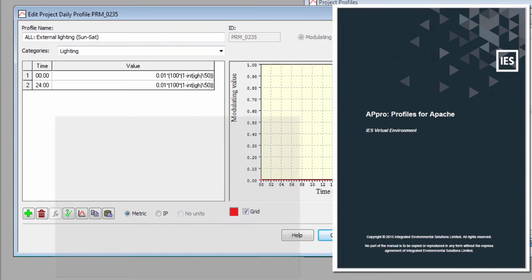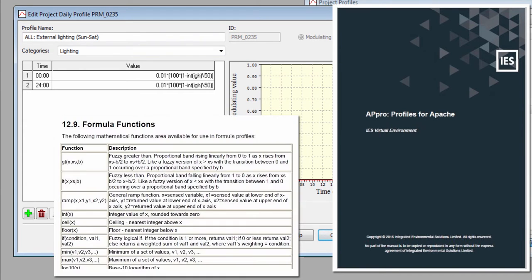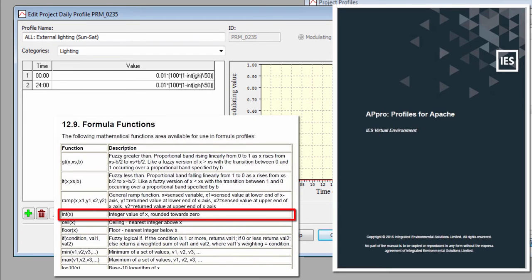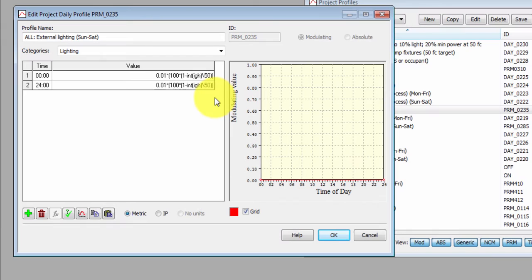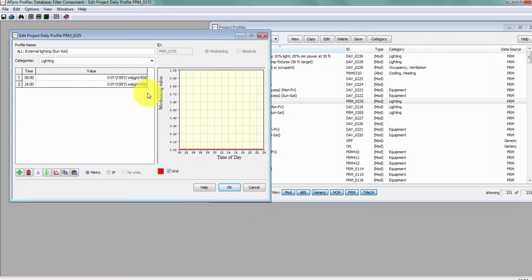The operator INT means integer and is going to take the integer value of the global radiation rounded down. If the value of this formula is greater than 0.5, the exterior lighting will be turned on. A value of less than 0.5 will signal off and the exterior lighting will be turned off.